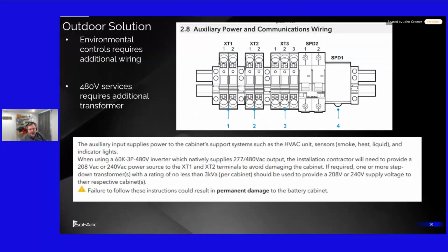When installing the outdoor version, it is a little bit more complicated than the indoor version. The indoor version is just put the battery modules in a rack, put a bunch of cables in the only position that they can go into, and turn the system on. With the outdoor system, you have to run power out to the auxiliary power to power that air conditioner unit and the cabinet environmental controls like the smoke and heat detector. And more on this for 480: for 208, you just have to plan on running some auxiliary power from the facility. For 480, it requires an additional transformer. More on that in a minute.